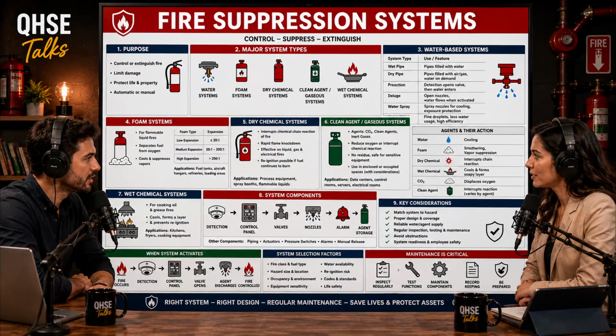The industry shifted to clean agents. There are two main categories now. First, inert gases like argon or nitrogen. These work by lowering the oxygen concentration, but they're much safer for human exposure than CO2. And the second category? Synthetic halocarbon agents like FM200 or fluorinated ketones like Novec 1230. These are chemically engineered to mimic halon. They put out the fire rapidly, leave zero residue, but they're designed with an ozone depletion potential of exactly 0.